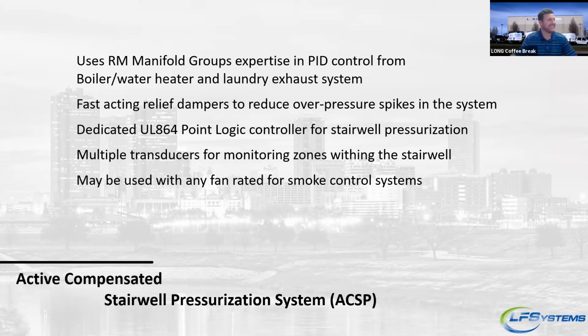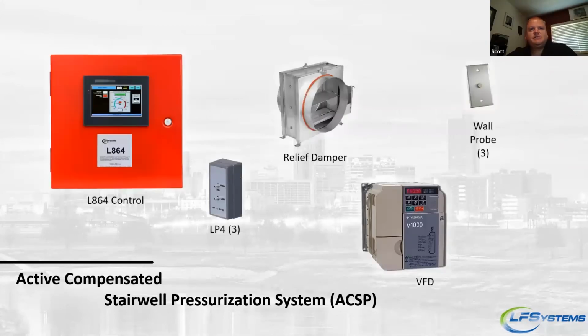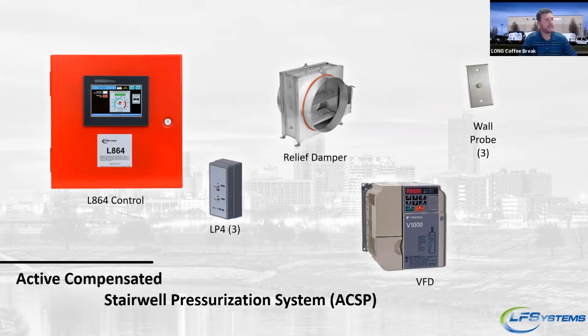There you go. So let's take a look at one of these systems. We call it our Active Compensated Stairwell Pressurization System, or ACSP for short. It consists of an L864 controller, up to 3 pressure transducers, a modulated relief damper if needed, a VFD, and wall probes. So Scott, in this scenario, we would typically provide a Yaskawa Z1000 without bypass, but when we have the L864 controller integrated in the smoke management system, it seems like we can simplify the VFD on our end and go down to just our standard V1000 drive.